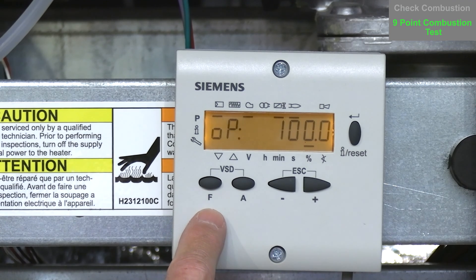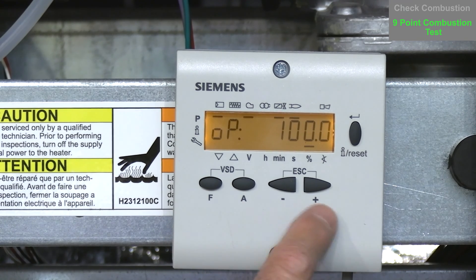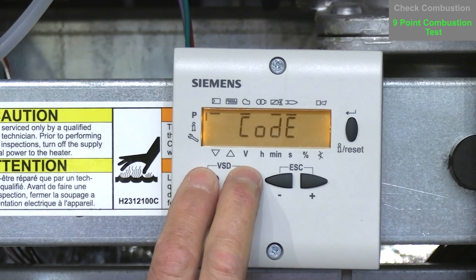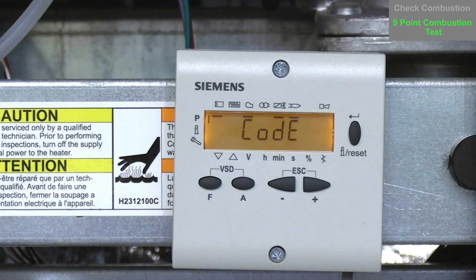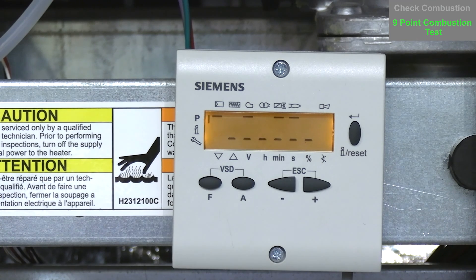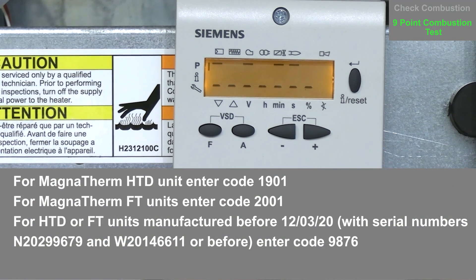On the pressure regulator, there is a manifold tap. Install your manometer on the downstream side of the gas valve — otherwise known as manifold pressure — and zero out your manometer. To log in to the AZL control, press the air and fuel buttons simultaneously until a code prompt appears. You'll see seven dashes and then type in your code. For a MagnaTherm HTD the code is 1901; for a MagnaTherm fire tube it's 2001. For HTD or FT units manufactured before 12-3-2020, the code is 9876.